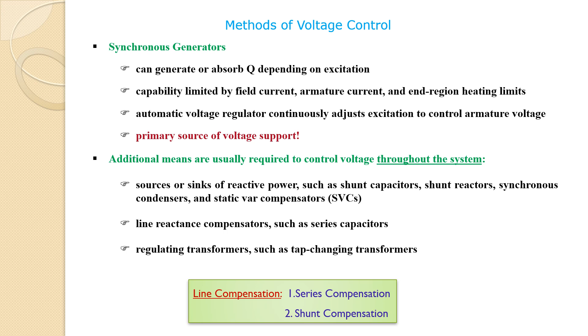The performance of EHV AC transmission systems can be improved by reactive compensation of series type. It consists of capacitors connected in series with the line at suitable locations. Series capacitors reduce the series reactance of the lines and act as line compensators. The compensation of lines helps in improving the system stability and increases the transmission capacity, that is, the efficiency of the system.